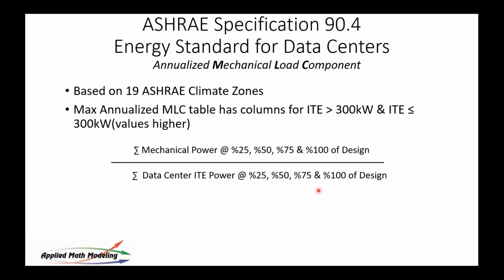So now not only are you taking a look at the ratio of, really, this is an inverse of COP. It's a COP number. It's upside down. But the point is it's ratioing the mechanical power to cool compared to what it's trying to cool, the IT power, at 4 points. The reason for the 4 points is to understand how that cooling system behaves itself at low IT loads. This is something that often happens. You design the cooling system for a data center to match worst case conditions, and then you never load it to worst case conditions, and so it never runs right. The cooling efficiency is never high because everything is way off its design specification.